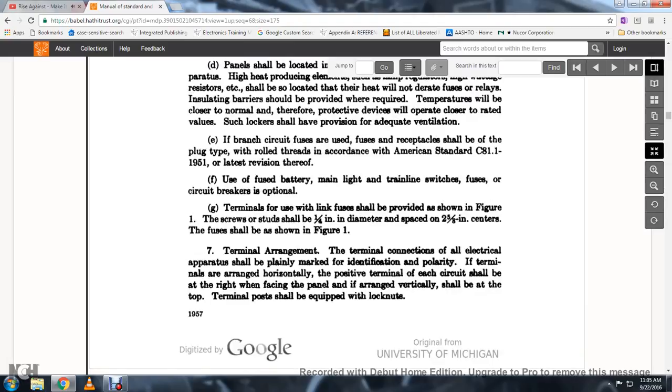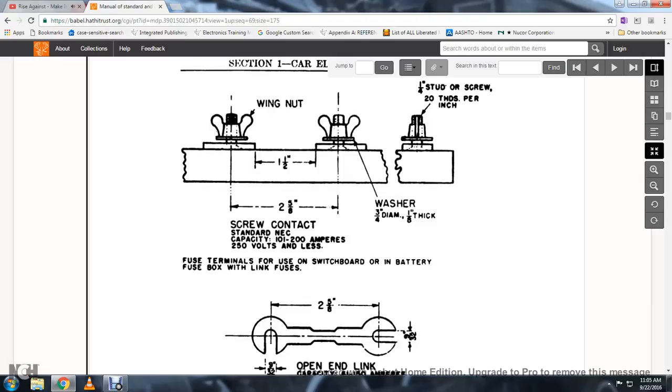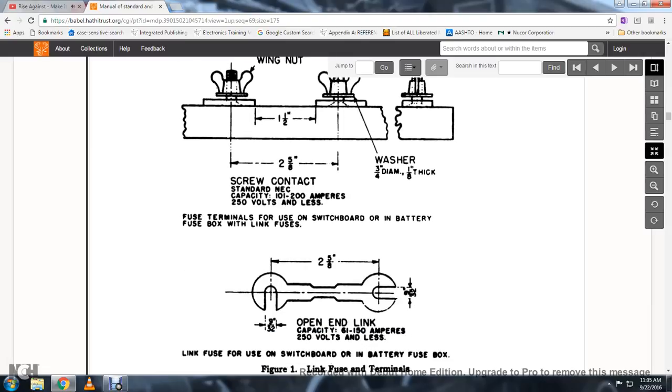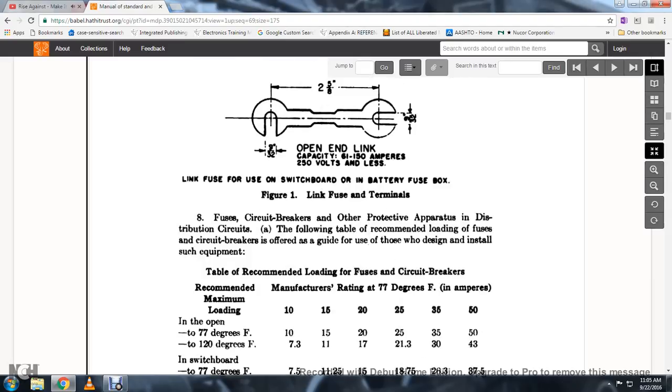Terminal Arrangements: The terminal connections of all electrical apparatus shall be plainly marked for identification and polarity. When terminals are arranged horizontally, the positive terminal on each circuit shall be at the right, and when facing the panel arranged vertically, shall be at the top. Terminal posts shall be equipped with lock nuts. This shows screw contacts, wing nuts for use with terminals for switchboards on battery or fuse box links. This is a link fuse terminal on the switchboard or battery fuse box.